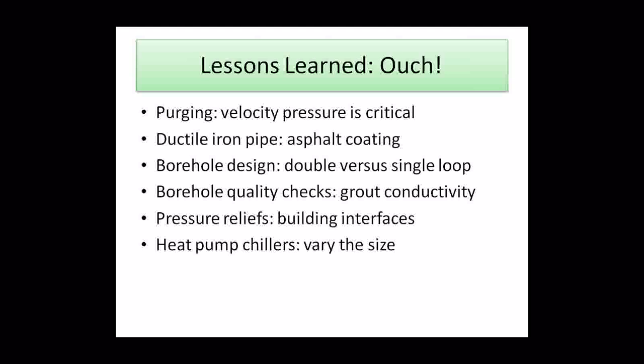Every batch is tested just to make sure we're getting the right mix. Our building interfaces, the reason I point this out, our pressure is so intensified now that when we turned the system on, some of our pressure reliefs blew off, and we had water all over mechanical rooms, so we had to go through and adjust all that.